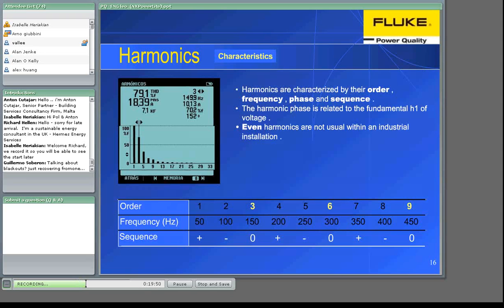Harmonics and unbalance generate the negative sequence. Negative sequence harmonics, like the fifth harmonic, have the characteristic to generate a counter field which reduces the efficiency of rotating machines. In turn, the zero sequence harmonics, triple harmonics, or multiples of the third harmonic, add themselves in the neutral.